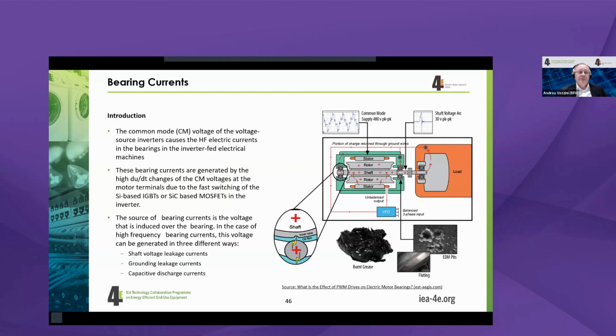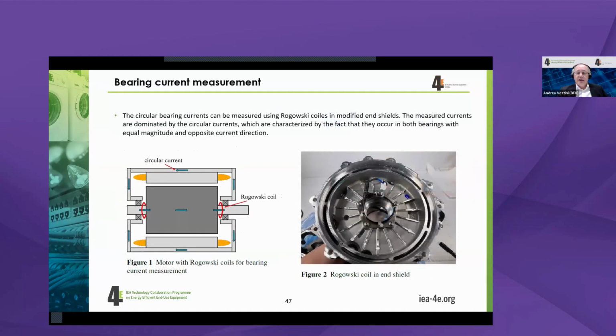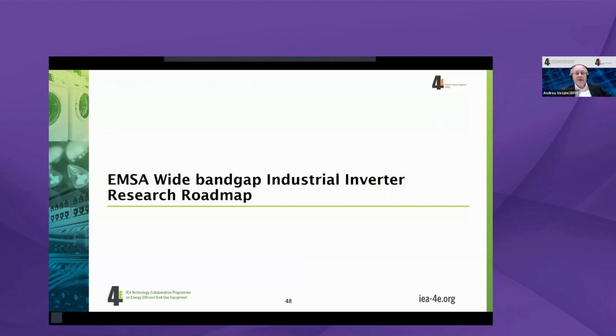Another ongoing test is the impact of the high switching speed of the common mode voltage supply, which will have an impact on the bearing currents, and the bearing currents then create grooves inside the bearings, and the impact can be seen there. And we are measuring these by adding some Rogowski coils inside the end shield of the motor to detect how much impact we have from this.